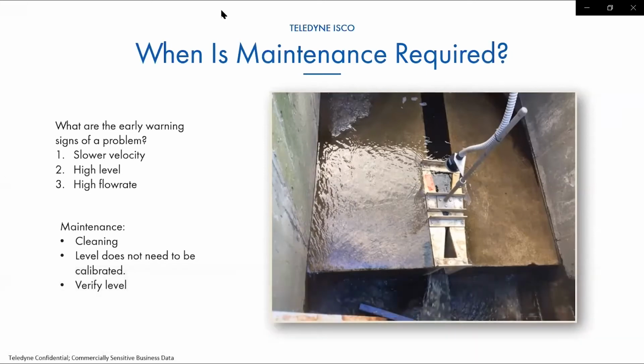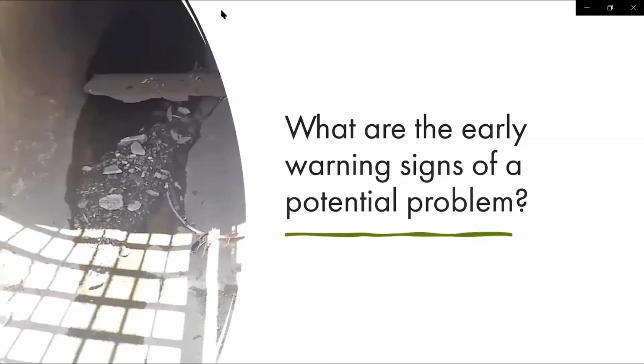So if this was a problem that continued to happen, I would highly recommend putting a secondary sensor upstream. And so you can actually use the velocity to help determine when you have a problem, or the level. And so, looking at your data is going to show you that you've got reduced velocity, higher levels, and then you should get somebody out there to do some maintenance. So what are the early warning signs of a potential problem?